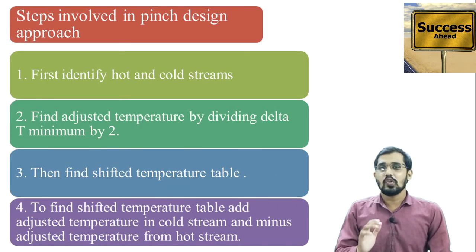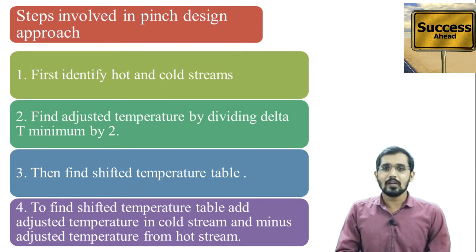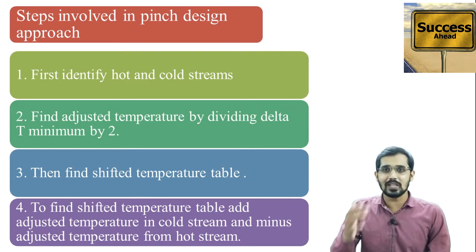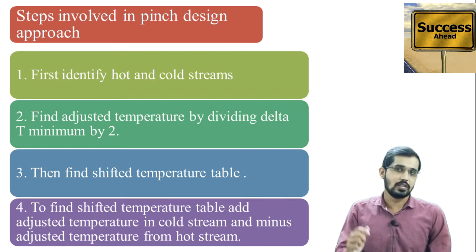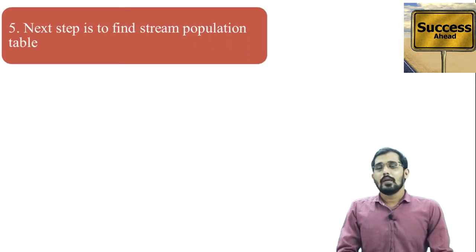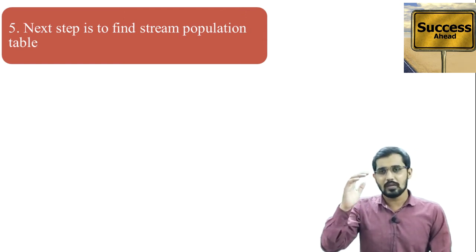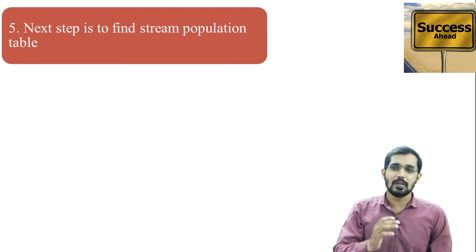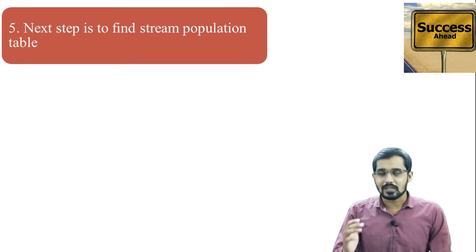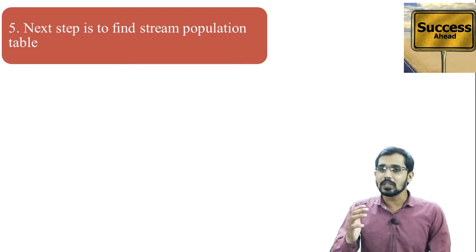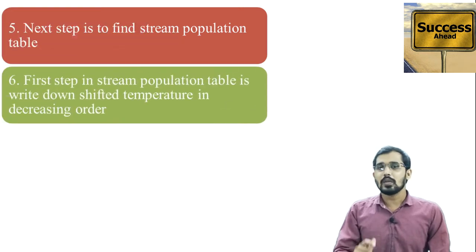To find the shifted temperature table, add the adjusted temperature to the cold stream and remove the adjusted temperature from the hot stream. The next step is to find the stream population table, where we calculate various ΔH values, Cpc values, Cph values, and extra utility values. I will explain all these steps now.